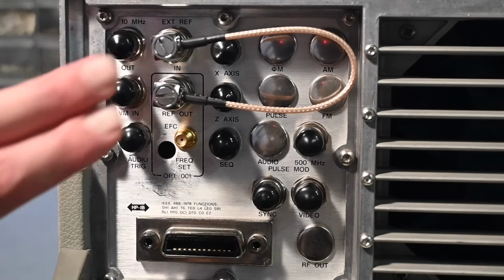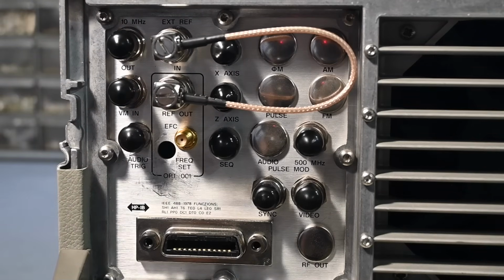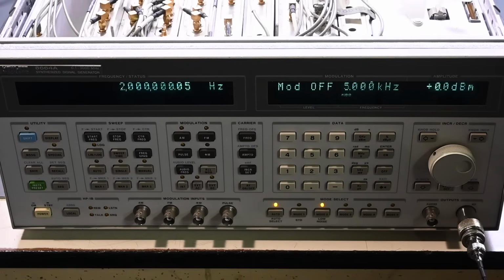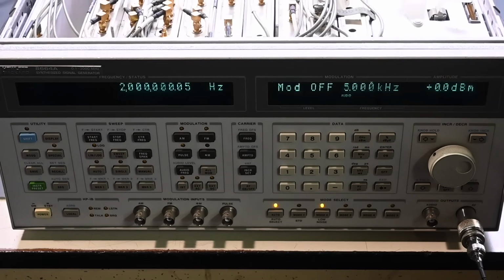All right, so I found this short coax jumper. So let's connect the signal generator to the frequency counter and see if the frequency accuracy has improved. All right, the oven light just turned off, so at least the oven is up to temperature, but the high stability time base probably hasn't completely stabilized until the instrument runs for a while. But nonetheless, the frequency accuracy looks very good now. So I think I should rerun the calibration procedure with the high stability time base properly connected. But you can see the RF output is set to 2,000,000.05 hertz. And let me move you up to the frequency counter.